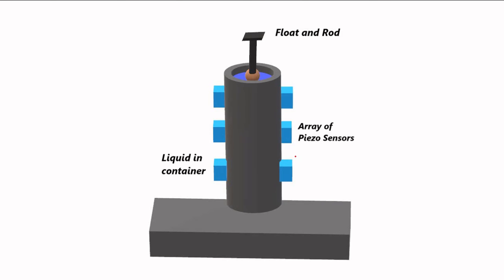For continuous level tracking, we have a series of piezoelectric sensors connected together, giving us the level at multiple points. Here I have only mentioned three sensors, but it can be 5, 10, 15, or 20 depending on the height of the container. All these piezo sensors are placed at fixed separation gaps — for example, at y = 0 m, y = 5 m, y = 10 m, and so on — giving us the level of the liquid continuously.